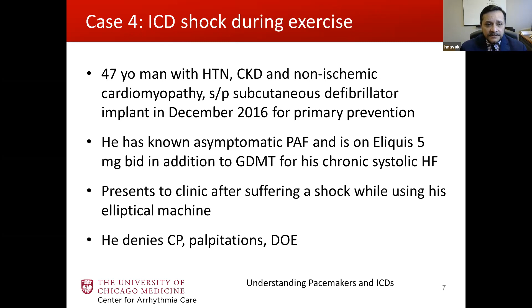So for those of you who are not familiar with the subcutaneous defibrillator, it's a totally non-transvenous system. The generator is generally placed in the mid-axillary line, and the lead connected to that generator is tunneled underneath the breast, the chest, and so it sits right above the sternum. And the device senses what we call subcutaneous electrograms or subcutaneous signals. And the sensing is programmed either primary, secondary, or something called alternate.